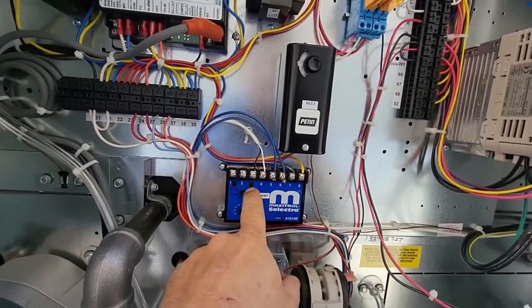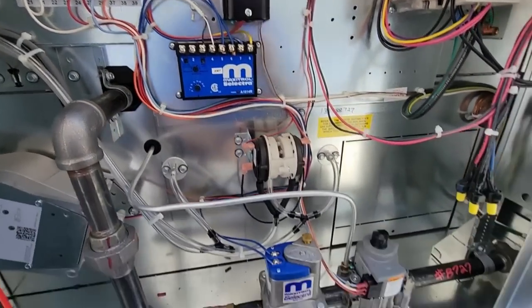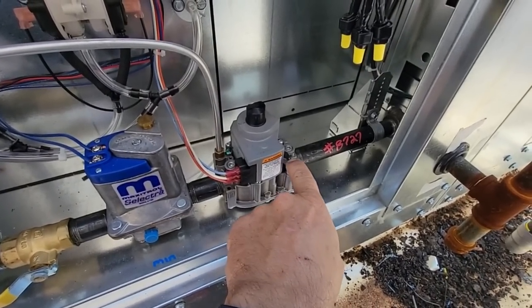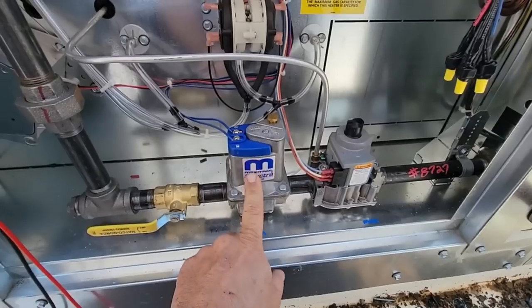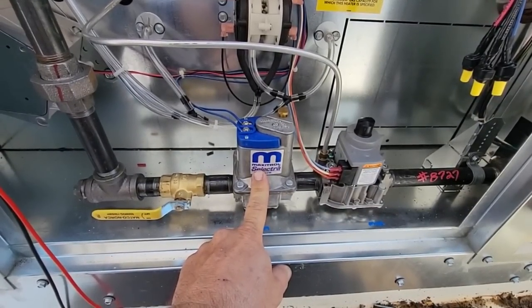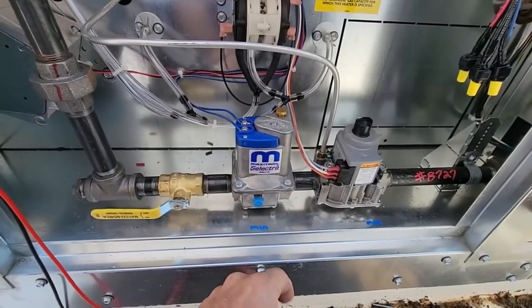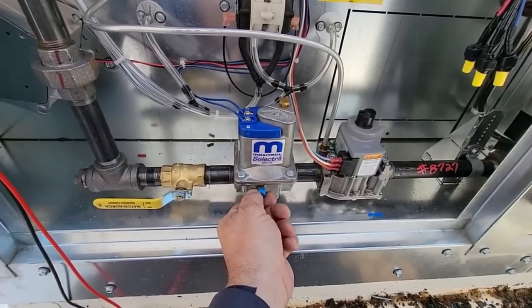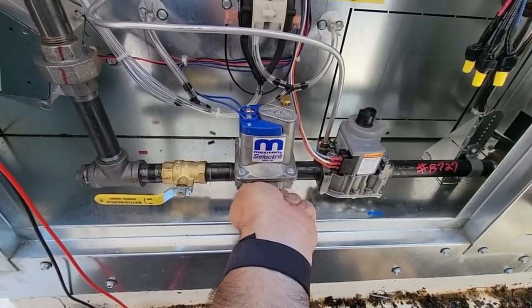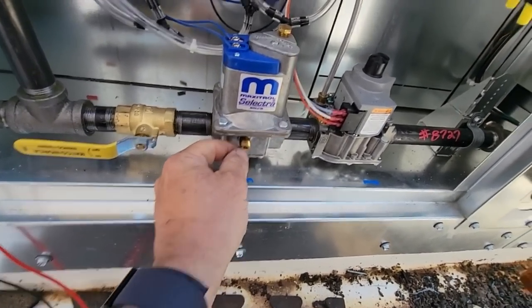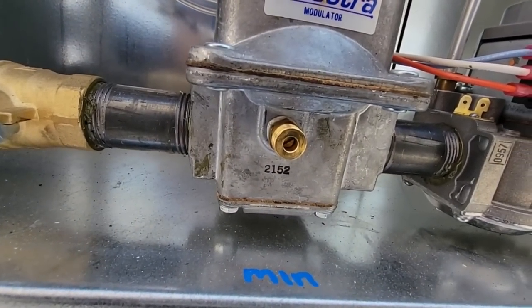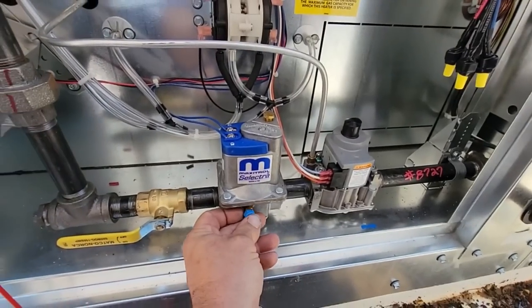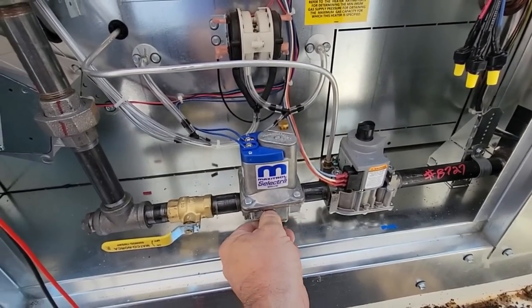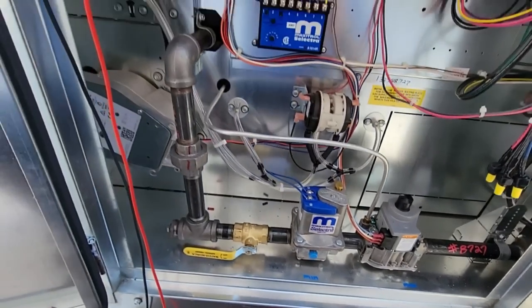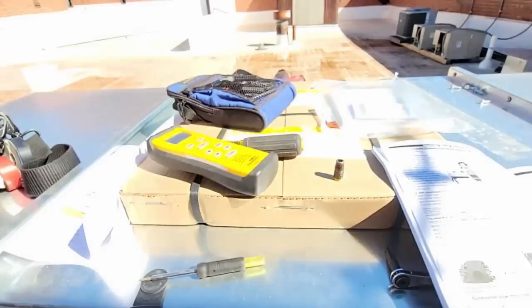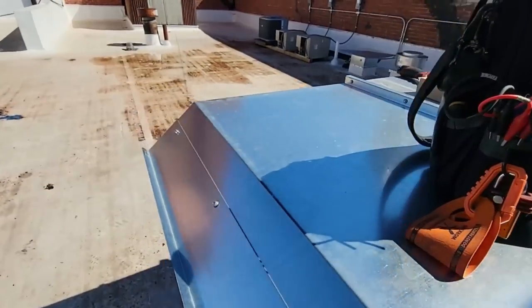Just to recap it, we took off 3, that put it in maximum fire, and we adjusted maximum fire here at the main gas valve. This is going to modulate open and closed so that it can maintain that temperature rise. And then your minimum position is down here, which I'm not going to set today because of the weather and stuff. It's not going to be accurate anyway, but you actually will close that down, and generally you set it up so it has a ribbon across the burner. It'd be really difficult to see it.